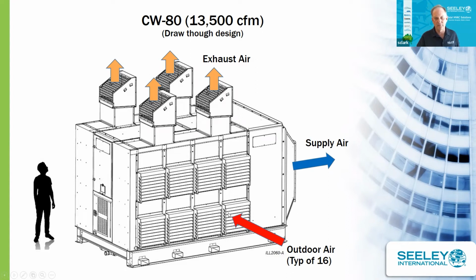We can go up to a MERV 13 filter. So we have the outdoor air coming in through all these inlets. And then on the opposite side, there's another 8 heat exchangers for a total of 16. And then we have our exhaust fans on the top. Our H15 units are a blow-through design. This is a draw-through design.